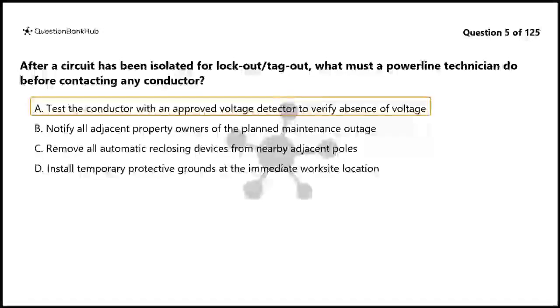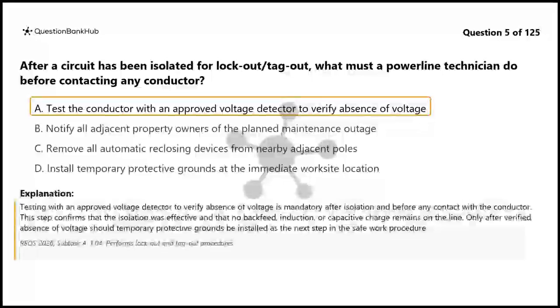The correct answer is A. Testing with an approved voltage detector to verify absence of voltage is mandatory after isolation and before any contact with the conductor. This step confirms that the isolation was effective and that no backfeed, induction, or capacitive charge remains on the line. Only after verified absence of voltage should temporary protective grounds be installed as the next step in the safe work procedure.